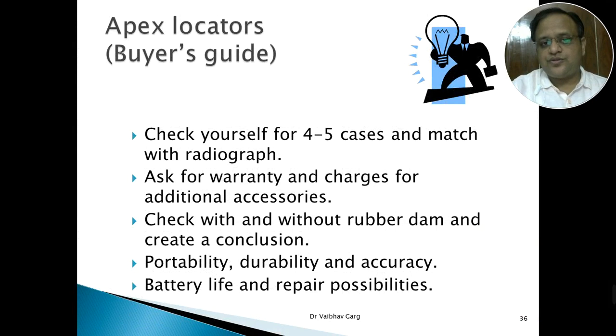So how should you buy an apex locator? I'm talking from a clinician's point of view. When you plan to buy your apex locator, check it yourself on 4 to 5 cases and match its accuracy along with the radiographs. You should always ask for warranty and charges for additional accessories. Check with and without rubber dam how the accuracy is coming up and create your own conclusion. See to the portability, durability and accuracy of the instrument.